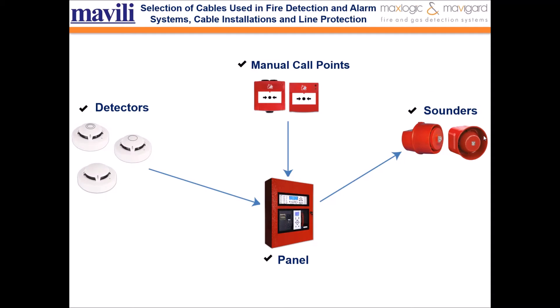First of all, what is the loop? Loop is the definition of a zone connected by cable, forming a single line with the device or devices on it. Each loop is independent of other parts of the system. Connection cables are managed by devices, monitoring and control devices on the circuit. In order to prevent natural or human errors that may occur and affect the whole system, the system should be controlled by dividing it into circuits.